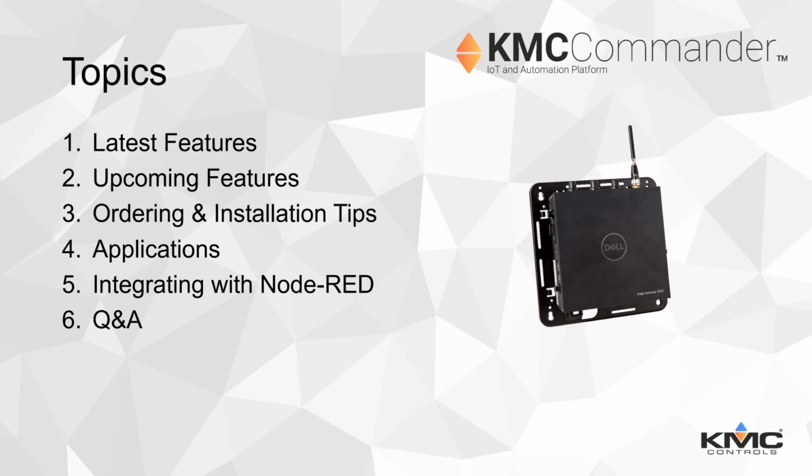Another item is, once you get to the job site and you set up the interfaces, port 1, and if you're going to change port 2 or whatever, or even use the Wi-Fi, you can only have one interface set up with a gateway. You need the gateway in order to talk to the cloud. So normally a lot of people set that up with port 1 in the dynamic. So if you set up port 2 to talk to your devices, your building network and that, do not put in a gateway in there.